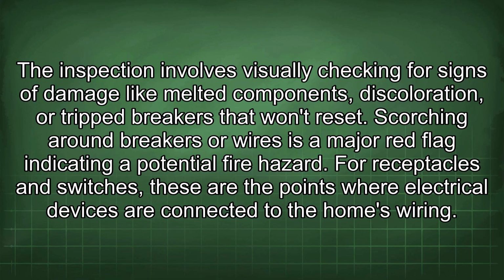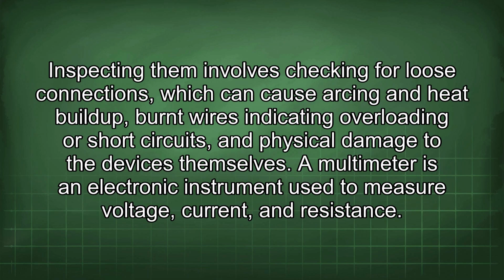For receptacles and switches, these are the points where electrical devices are connected to the home's wiring. Inspecting them involves checking for loose connections, which can cause arcing and heat buildup, burnt wires indicating overloading or short circuits, and physical damage to the devices themselves.